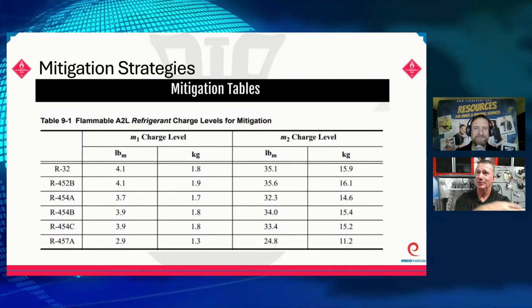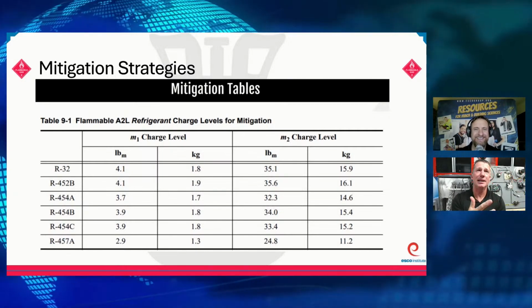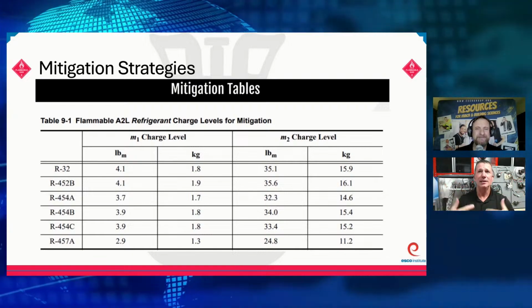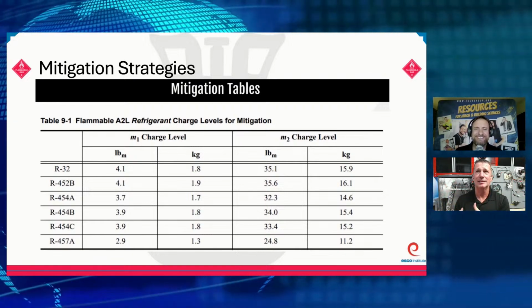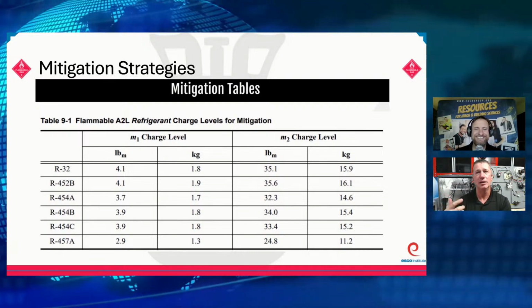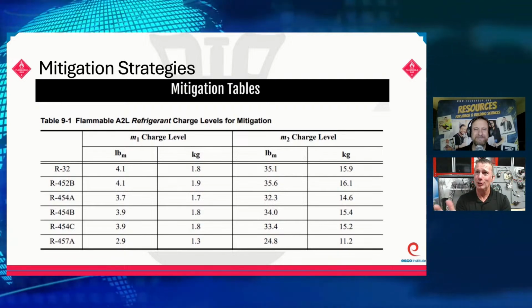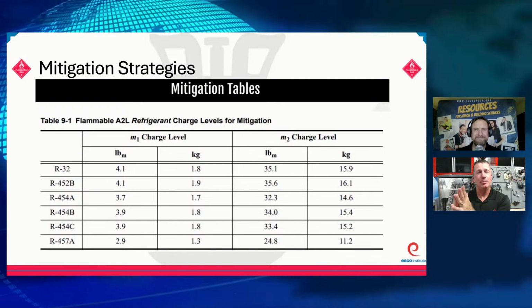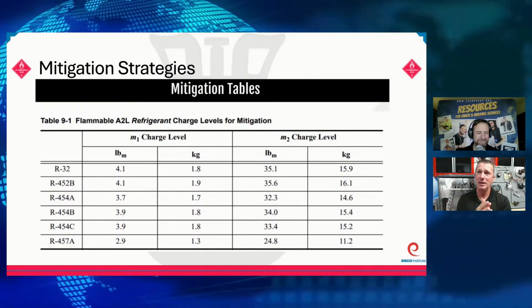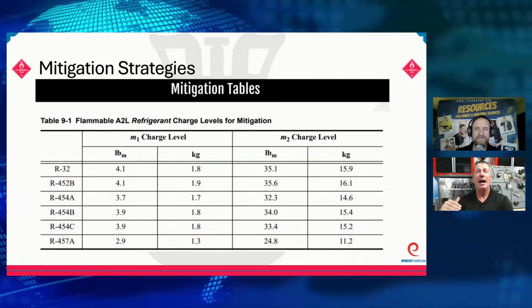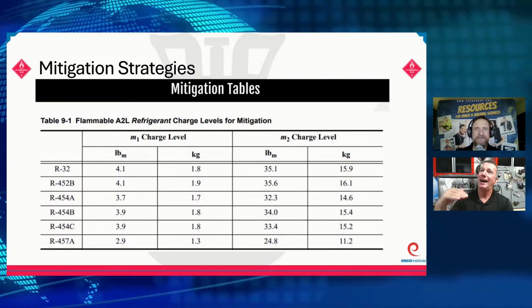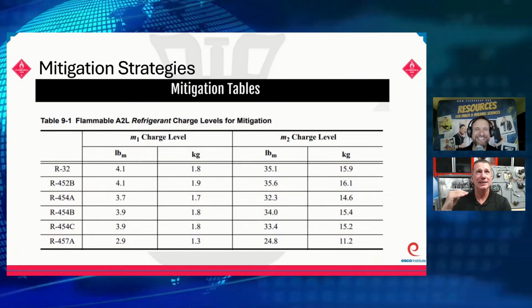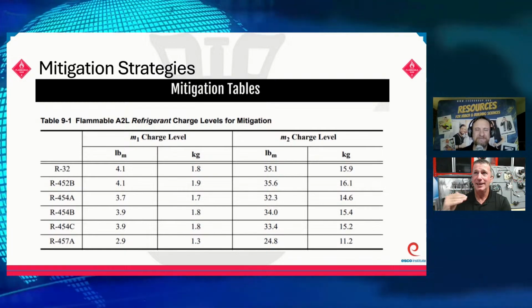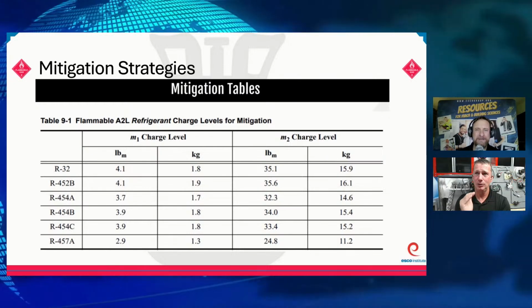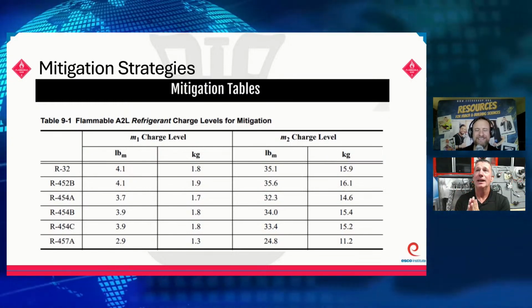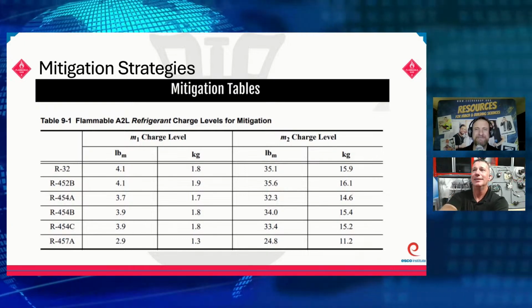So what is mitigation? Well, we've already talked about that in the gas appliances. Let's think about that from a refrigerant perspective, okay? I did this sequence of operation to mitigate any potential gases on that A3 natural gas or propane in our gas furnace. So what would we want to do as a procedure for when we go into the state of mitigation? The state of mitigation would be, okay, I have approached and I have met my lower flammability limit of this particular refrigerant. My sensor has detected enough that I should change my state to now a soft lockout, and I should have a sequence of mitigation. So let's all think about that, okay?